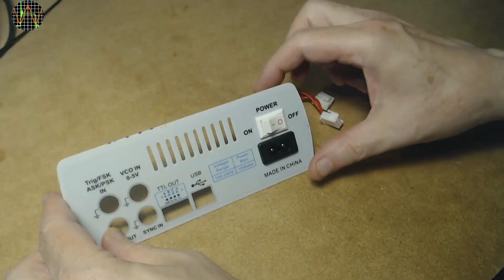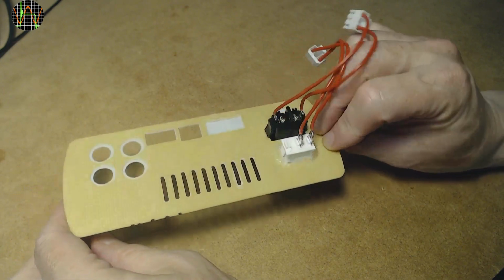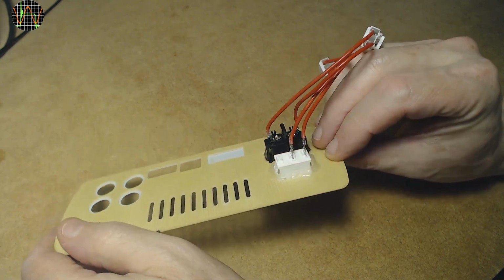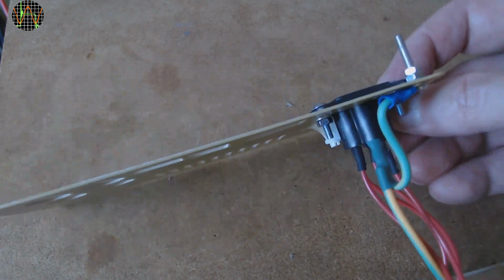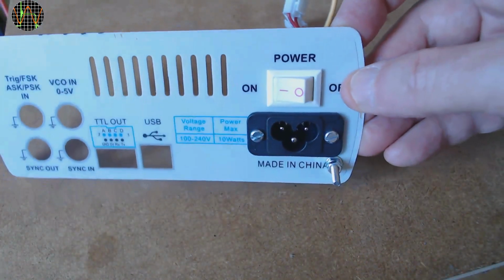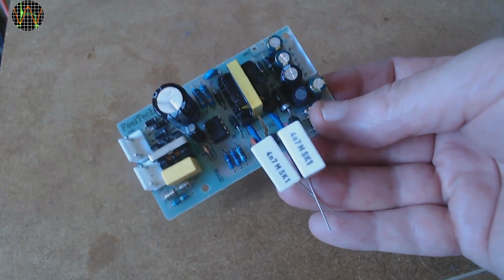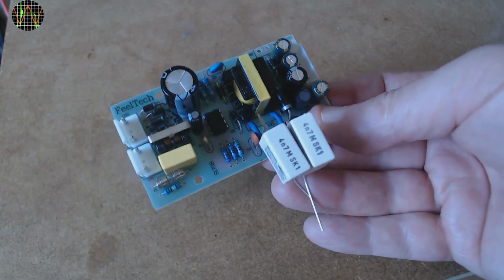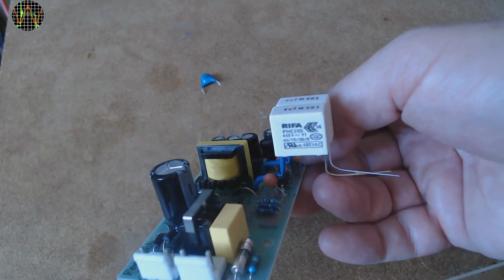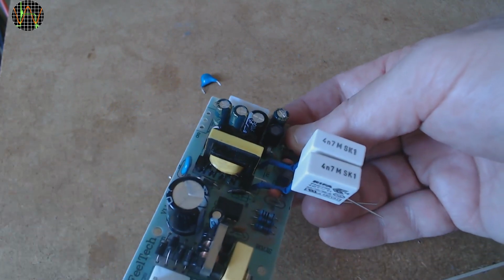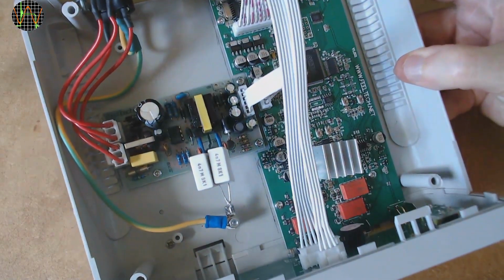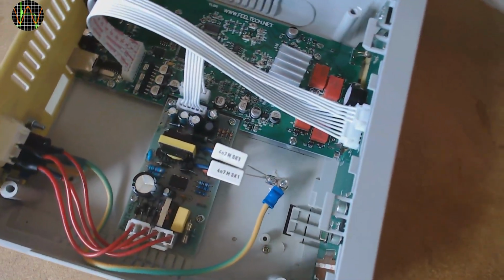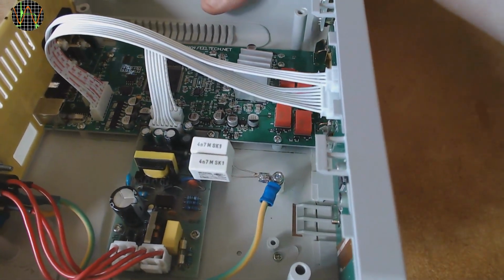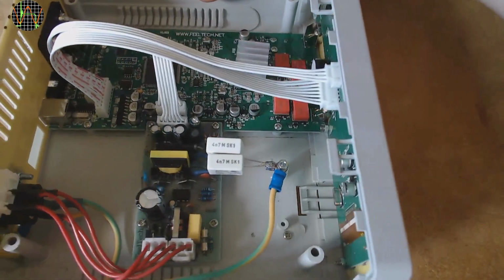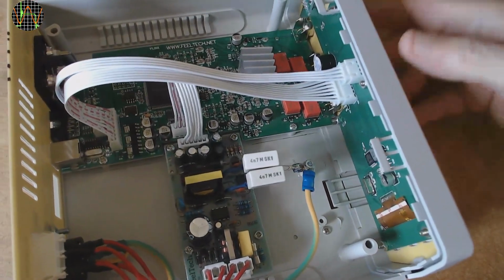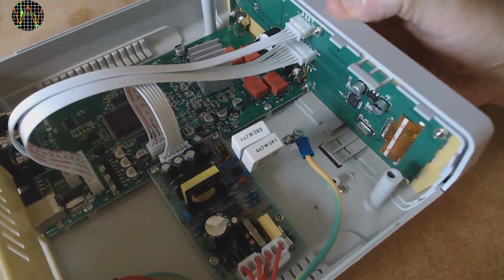The fix I suggested in that video was to replace the original 2-wire mains connector and lead with a 3-wire version that provides proper access to mains earth, remove the original y-capacitor, and instead add 2 y-capacitors, one lead each soldered into the PCB where the original y-capacitor was, and connect the other ends together with mains earth. While this greatly reduces the stray voltage problem, it does not remove it completely, and sometimes the output's capacitive coupling to earth causes other problems in a test setup.